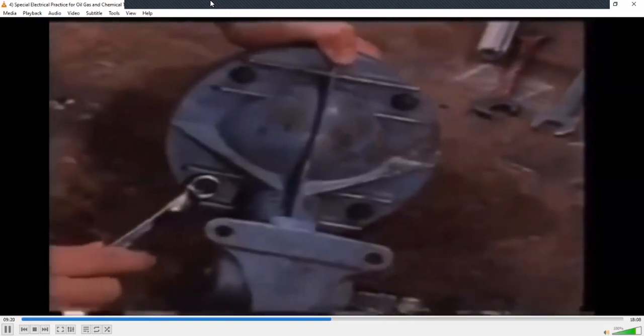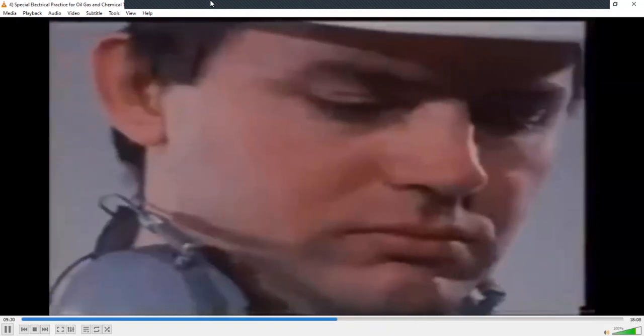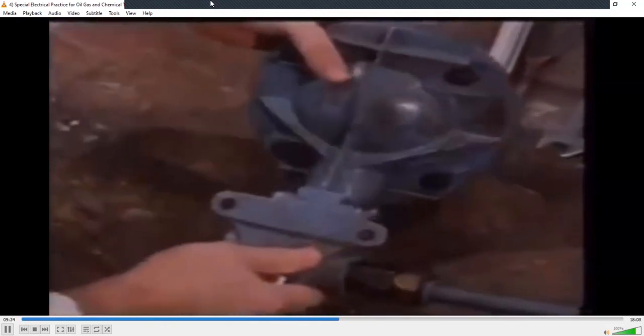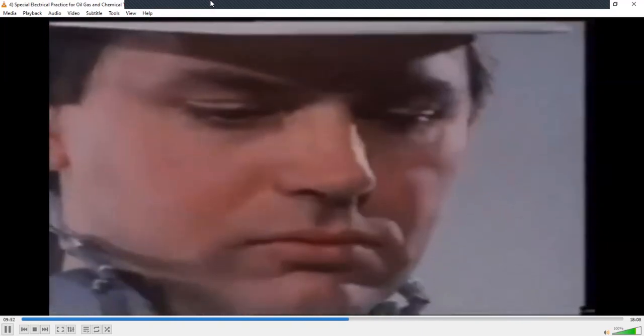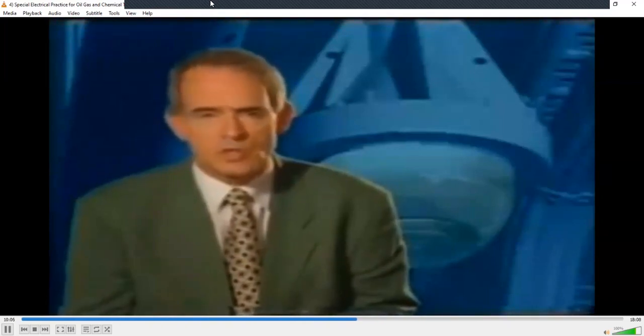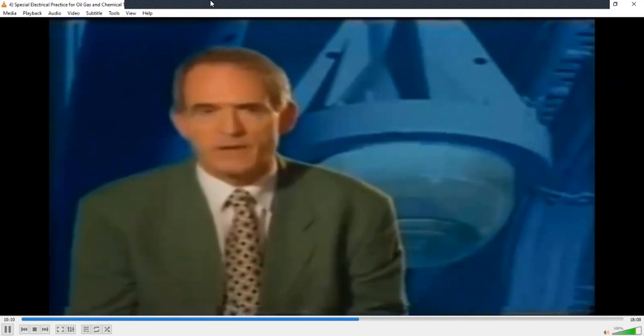If a broken stud has to be removed from a blind hole, great care must be taken to avoid damaging the internal thread or drilling through into the flame-proof enclosure. Broken or missing screws must be replaced by ones of the same diameter, thread, length, type, and quality of steel. Finally, check once again that the flame-proof gland is correctly tightened. Remember, the installation must not be changed in any way for any reason, as this may invalidate its certified safety level.